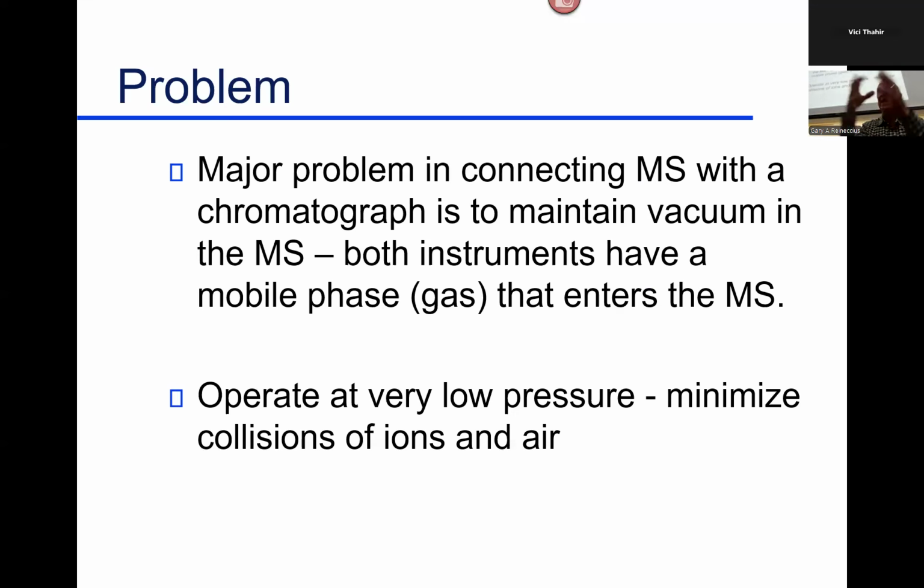There's a bit of a problem, because that little bit, maybe 1 microliter of solvent, expands to a tremendous volume. Oops, there went my vacuum. All of a sudden the vacuum in the system nosedives because of the solvent that just expanded and filled the instrument. It doesn't seem like it'd be a problem, but it truly is. A microliter of solvent can give you a very large volume. So how you separate whatever solvent system, whatever method you've got, and have your compounds is extremely important. And they also have to run under a vacuum.